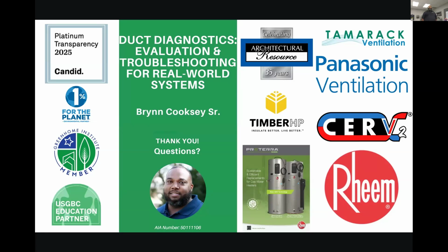So, if possible, we like to seal those, maybe using a solution like AeroSeal, but they are generally tight when you measure the return system back. So oftentimes, what we'll do when we replace a system, a heat pump or a furnace, we'll upsize the return to get more airflow to the air handler, but the band joists are a problem in this country.